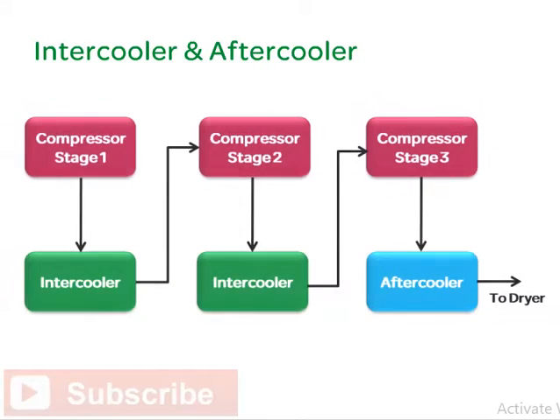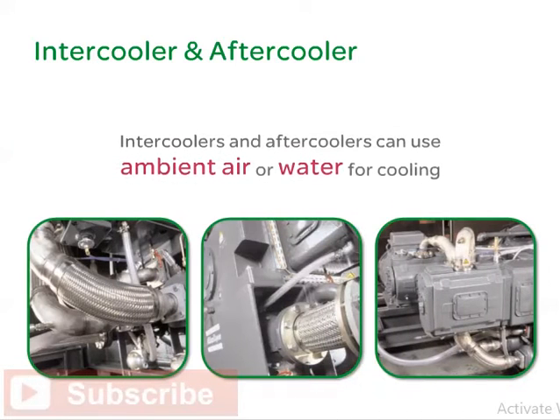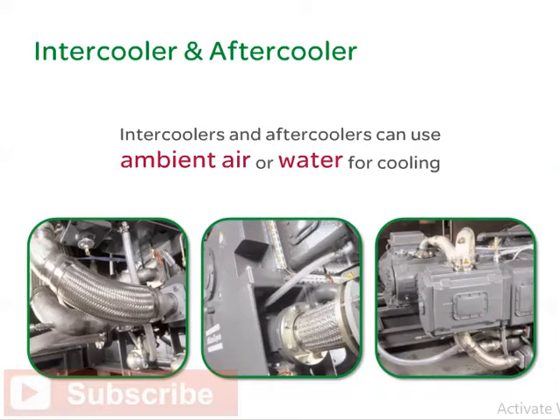In a multi-stage compressor, there will typically be an intercooler between each stage. This is a heat exchanger that removes the heat of compression before the air enters the next stage. As the air is cooled, the airstream may fall to its pressure dew point, and any additional cooling causes water vapor to condense out. Condensate is separated from the compressed air and drained out of the system. An aftercooler cools air leaving the compressor. Sometimes it is an integral part of the compressor package, but sometimes it is a separate heat exchanger. Intercoolers and aftercoolers can use ambient air or water for cooling.